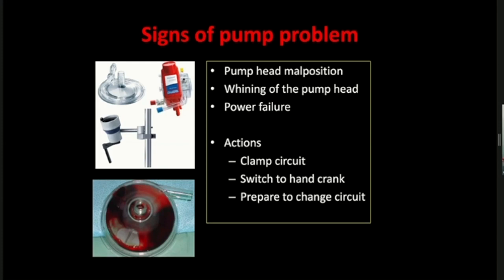In emergency pump failure — when the pump suddenly stops — you need to know how to clamp the line, remove the pump, change it to the hand crank, and perform this at the bedside. Bedside nurses are taught to do this. In recent years we have not encountered overt pump failure, but we do have pumps with thrombosis or clot formation that we can detect early. When detected, we electively change out the whole circuit rather than wait for the pump to fail and require emergency hand cranking.